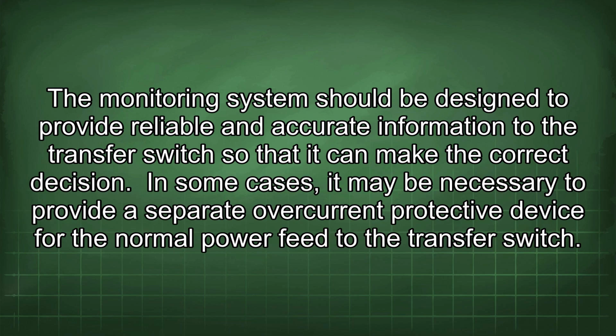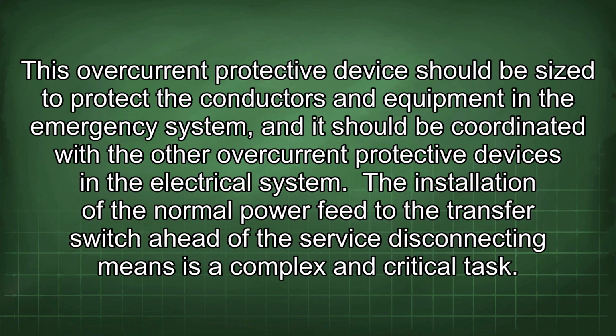In some cases, it may be necessary to provide a separate overcurrent protective device for the normal power feed to the transfer switch. This overcurrent protective device should be sized to protect the conductors and equipment in the emergency system, and it should be coordinated with the other overcurrent protective devices in the electrical system.